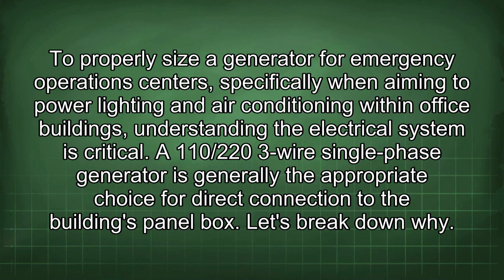properly size a generator for emergency operations centers, specifically when aiming to power lighting and air conditioning within office buildings. Understanding the electrical system is critical. A 110/220 three-wire single-phase generator is generally the appropriate choice for direct connection to the building's panel box.